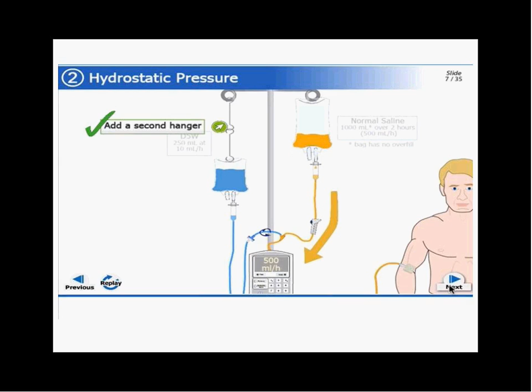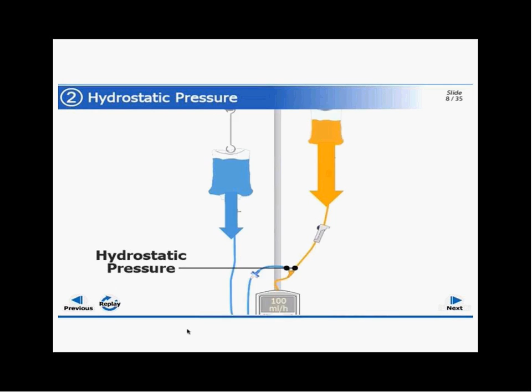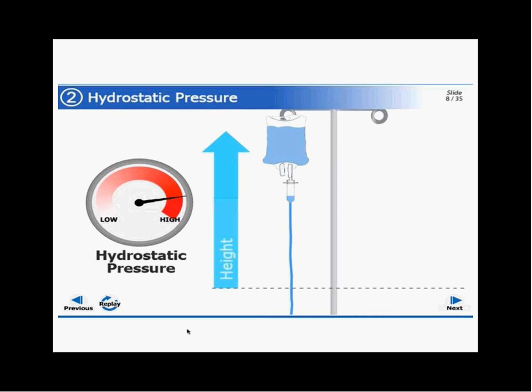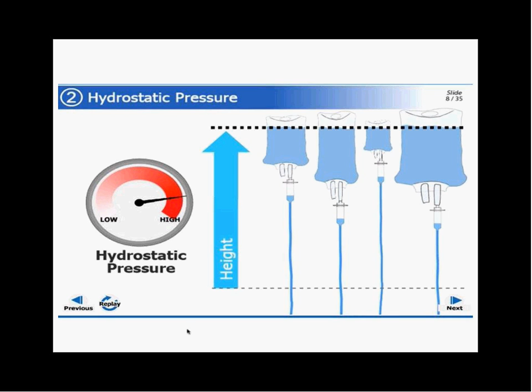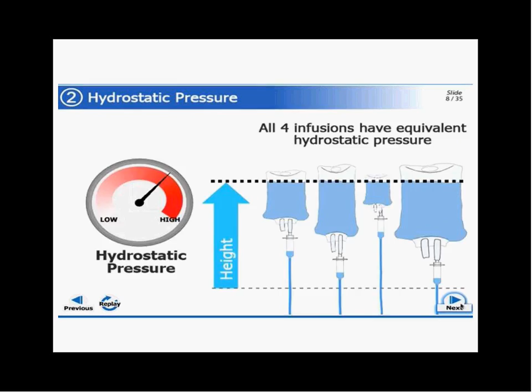Fluid in the tubing exerts a downward force due to gravity. This raises pressure in the tubing, called hydrostatic pressure. Pressure increases as you raise the bag relative to the pump. The size of the bag doesn't affect the pressure, only the height of the top of the fluid does.